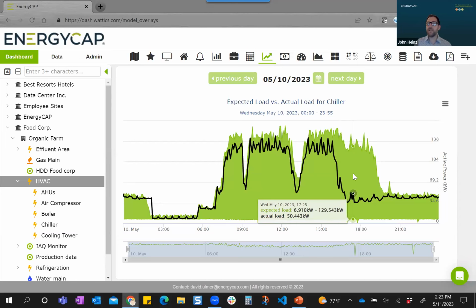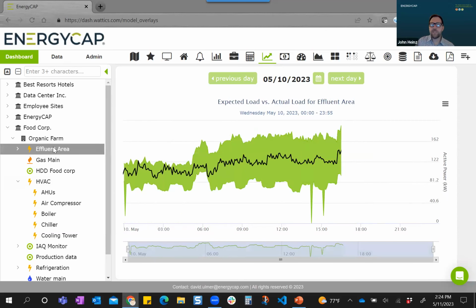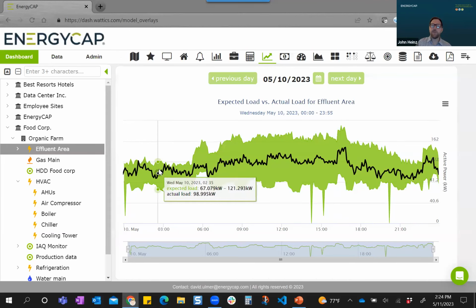So even though the Sentinel said, hey, generally you're doing this, which is in green, the organization now is starting to take some initiatives to have setback happen earlier in the day, and then they can start tracking the savings of this period here. So the Sentinel is really helpful, where if you go to any point, the profile just is different depending on what's a reasonable trend for that given point. So really helpful machine learning tools built in.